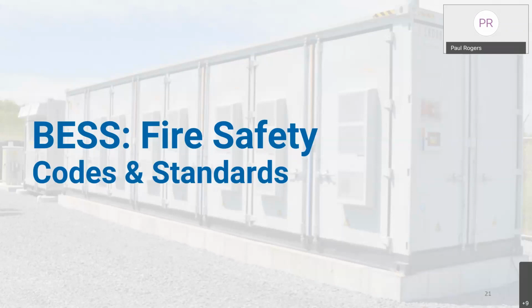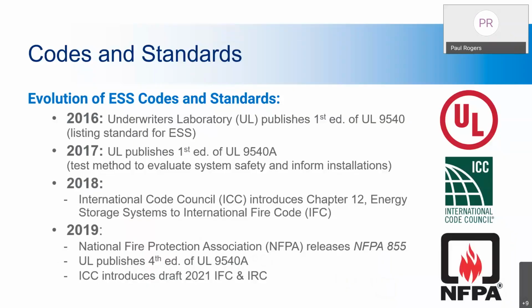As things started to develop, we wanted to know more about how the product is, and how do we know whether the inverter was actually going to be matched up to the batteries themselves. So the inverter had a standard on its own. UL came out with this thing called UL 9540, which just says the system works together, that the inverter is talking to the batteries and everything's working in conjunction as it should be. This way it's considered safe as far as how these things interact with each other.